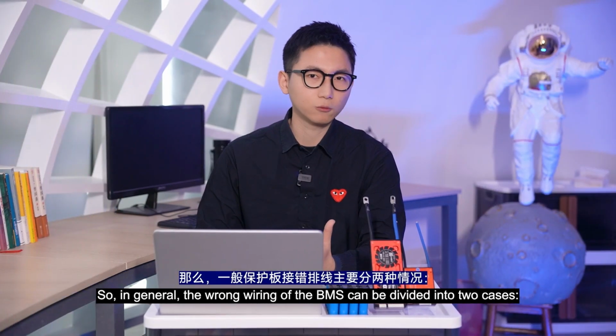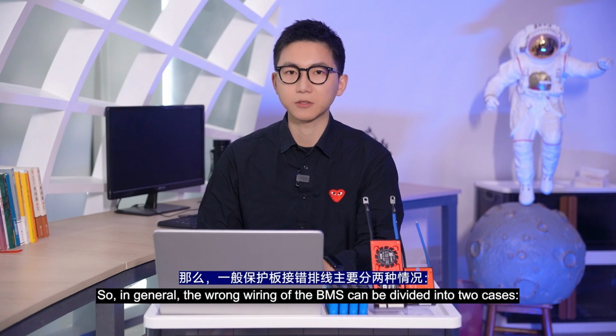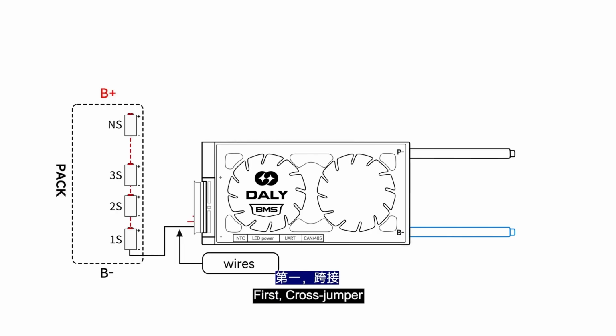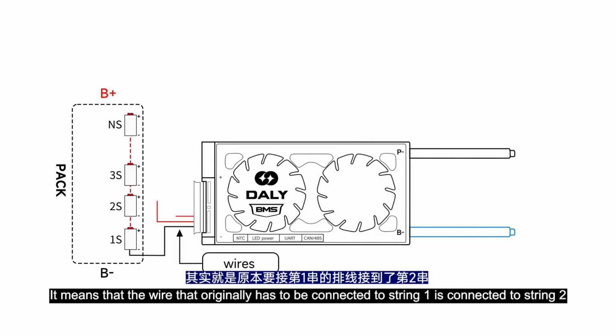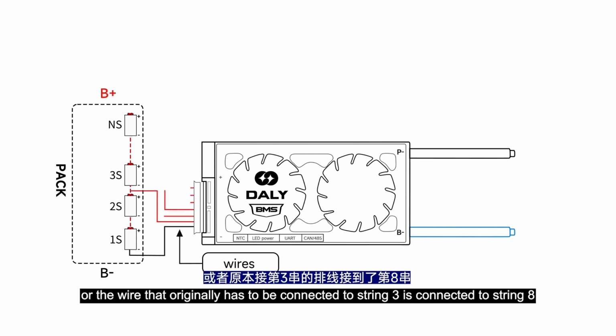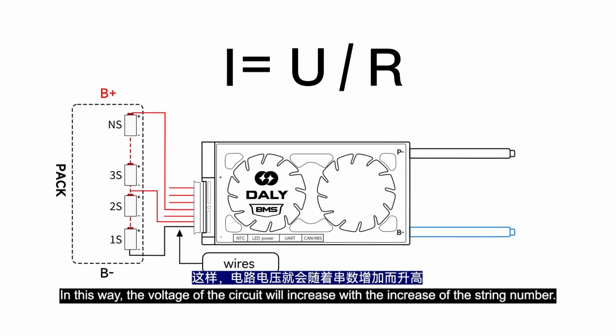In general, wrong wiring of the BMS can be divided into two cases. First, cross jumper: this means the wire that should be connected to string 1 is connected to string 2, or the wire that should be connected to string 3 is connected to string 8. In this way, the voltage of the circuit will increase with the increase of the string number.